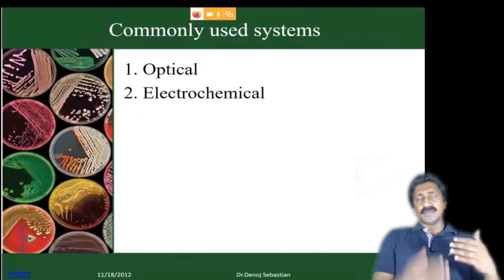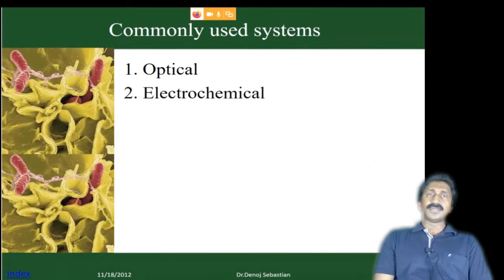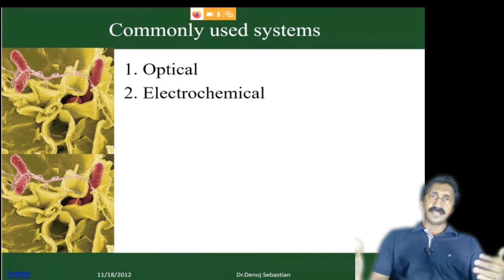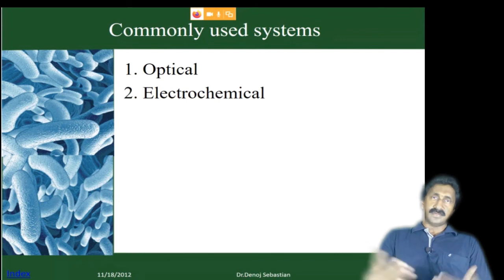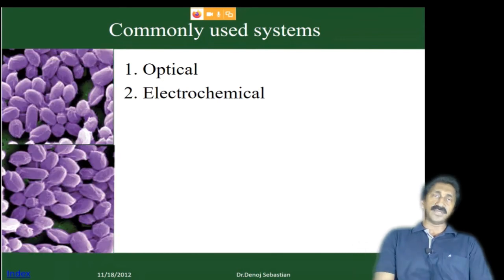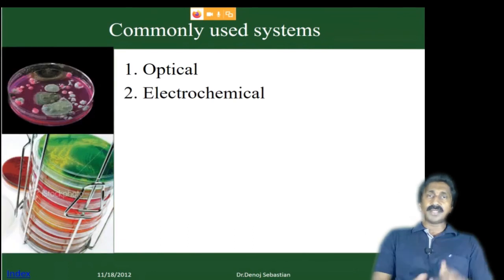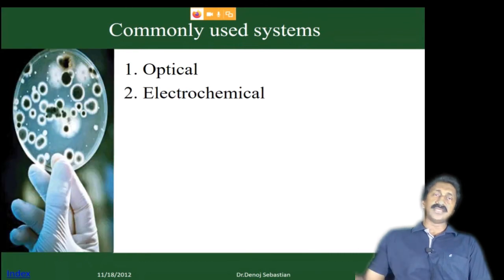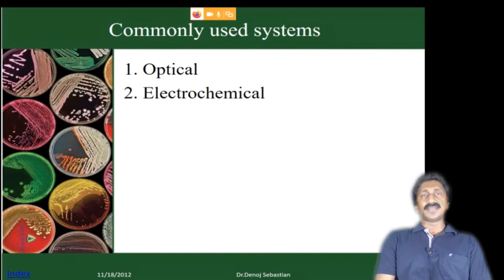So on the surface, which may be a gold-plated surface or something, onto which the receptors will be bound, if the analyte binds to that part, then that binding will result in an electrical potential change on the surface plasmons, which are flowing through the surface, and that change will result in the deflection of the light that is passed through the prism, and which will result in a change in the electrical output that is created for the graph. So that's how surface plasmon resonance works.